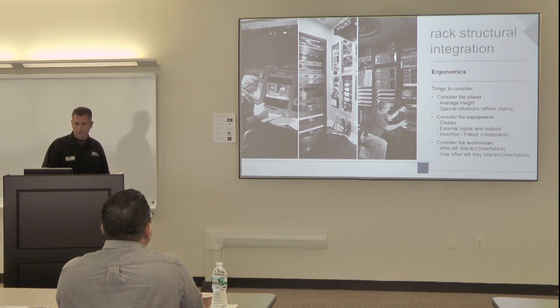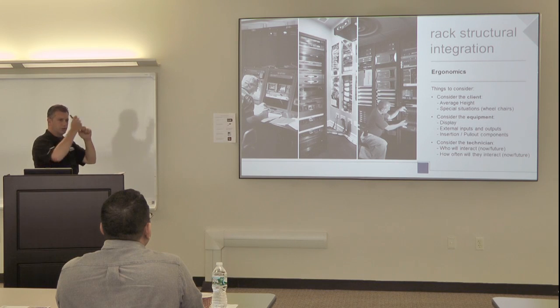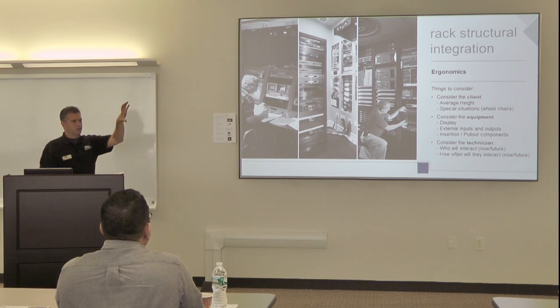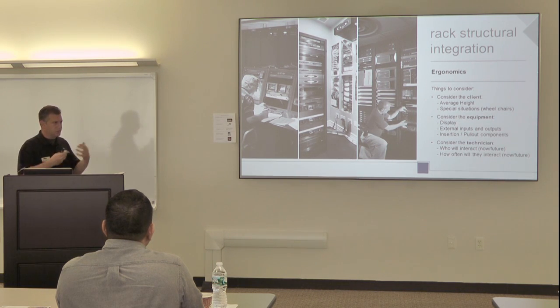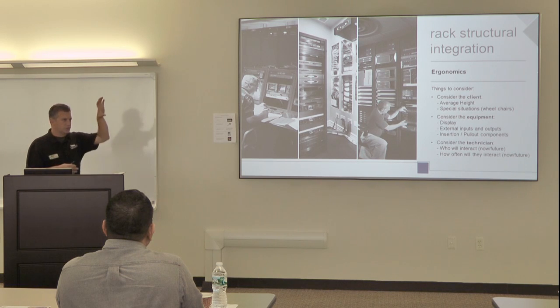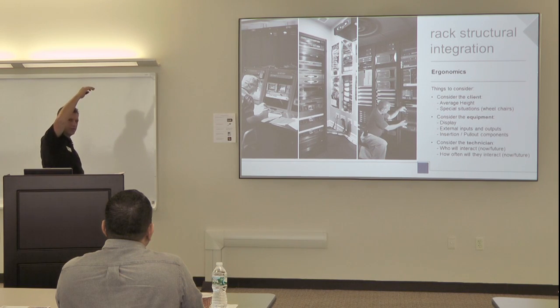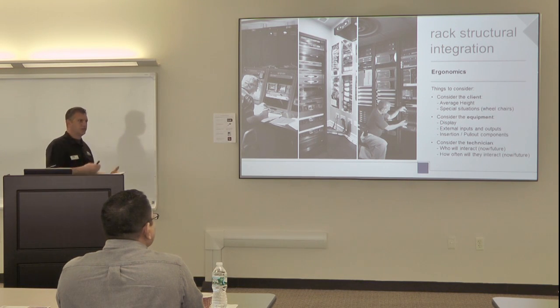Ergonomics is a couple things you need to look at. One, for the client: if there's something he's always touching or needs to turn on and off, you don't want to put that all the way at the bottom of the rack. Same with displays, you're not going to put them all the way top or bottom, so consider that in your rack layout. For the technician, think about how often he interacts with it in the back. You don't want something he needs a ladder for every time at the top of the rack. Put it where he can easily interact with it. So a couple of things to think about when laying out your racks.